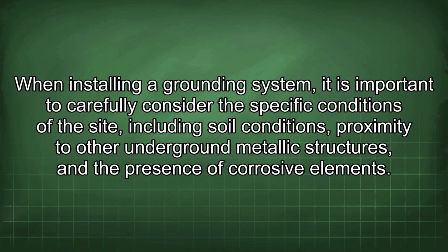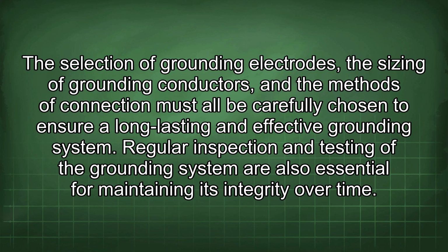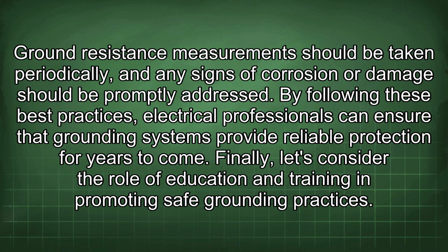When installing a grounding system, it is important to carefully consider the specific conditions of the site, including soil conditions, proximity to other underground metallic structures, and the presence of corrosive elements. The selection of grounding electrodes, the sizing of grounding conductors, and the methods of connection must all be carefully chosen to ensure a long-lasting and effective grounding system. Regular inspection and testing of the grounding system are also essential for maintaining its integrity over time. Ground resistance measurements should be taken periodically, and any signs of corrosion or damage should be promptly addressed. By following these best practices, electrical professionals can ensure that grounding systems provide reliable protection for years to come.